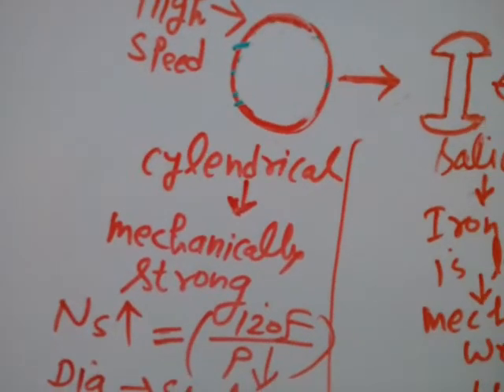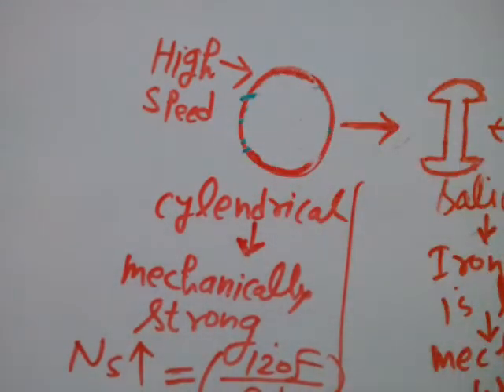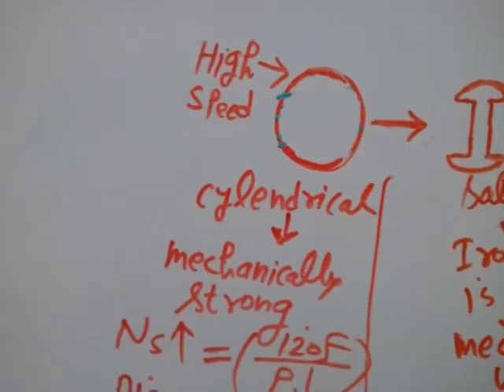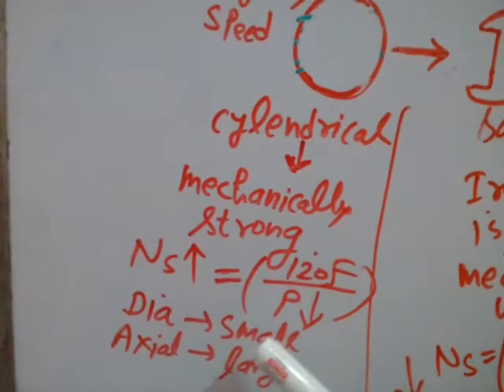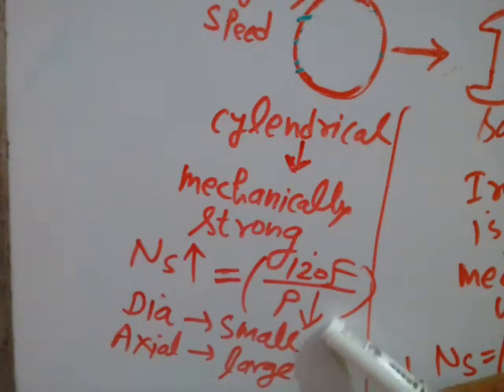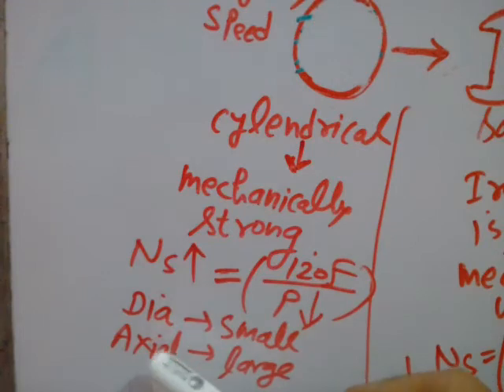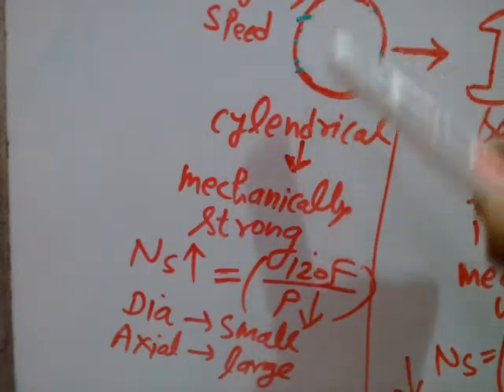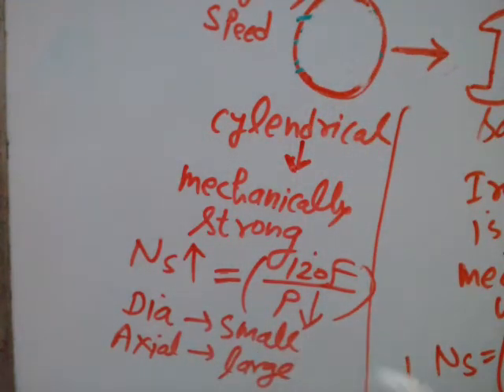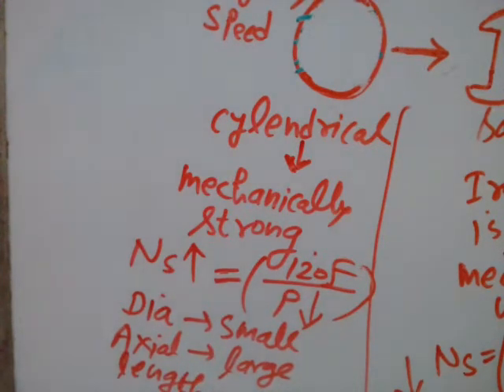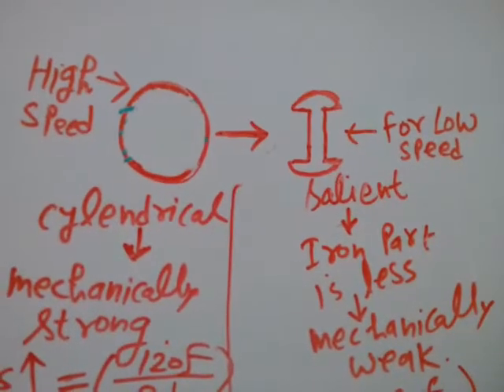Conversely, the cylindrical rotor is always used for high speed because its structure is mechanically strong, so it can be used for high speed applications. The number of poles will be less because speed and poles are inversely proportional. You have to accommodate a small number of poles on the periphery, so the diameter would definitely be small. When the diameter is small, the axial length must be large.